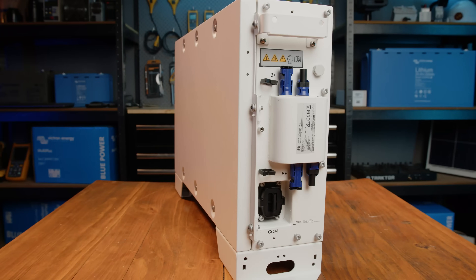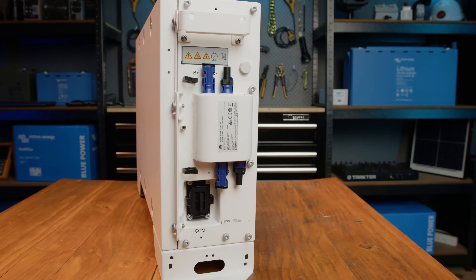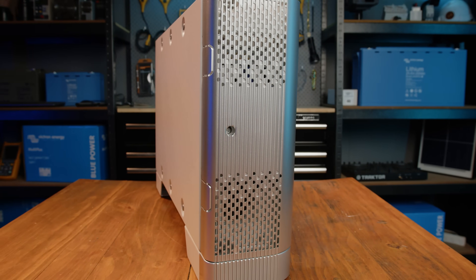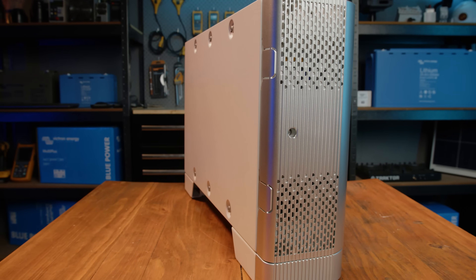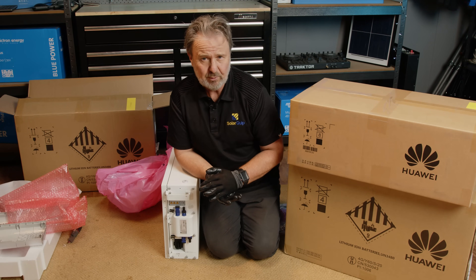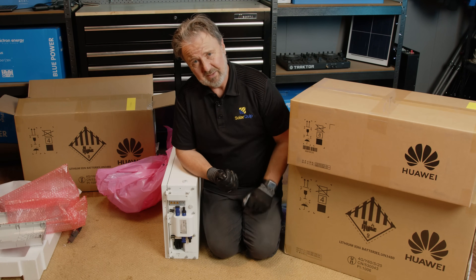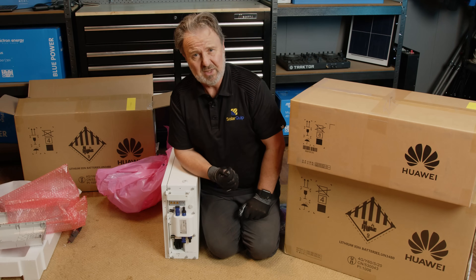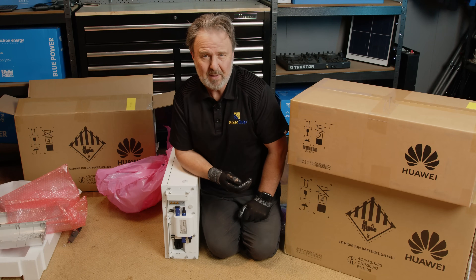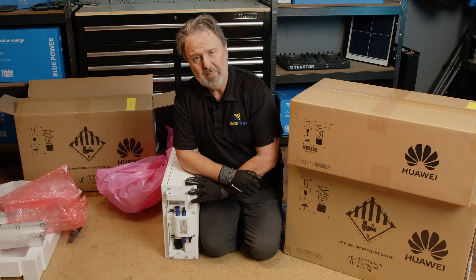The first thing you'll notice is that there is a male and female, and a male and female connector — that's because these batteries connect in a special way. Normally stackable batteries are connected in series, so as you add more in series your voltage goes up but your current stays the same. When charging a series connection of battery modules they all charge and discharge at the same rate, which seems okay, but you can't optimize for age with a series connection. If you have some battery modules added at a later stage, they have to be treated the same as all the modules in the string.